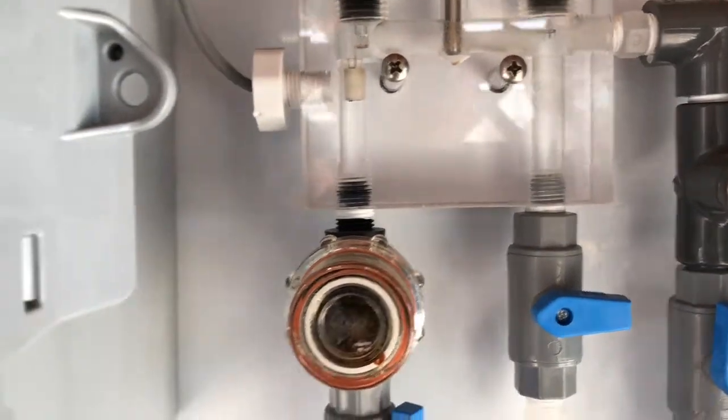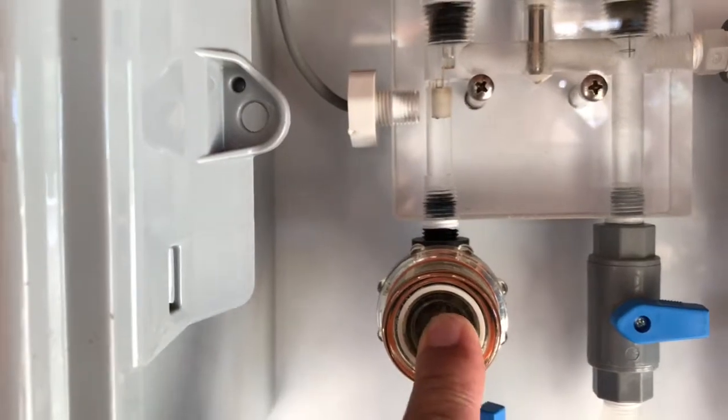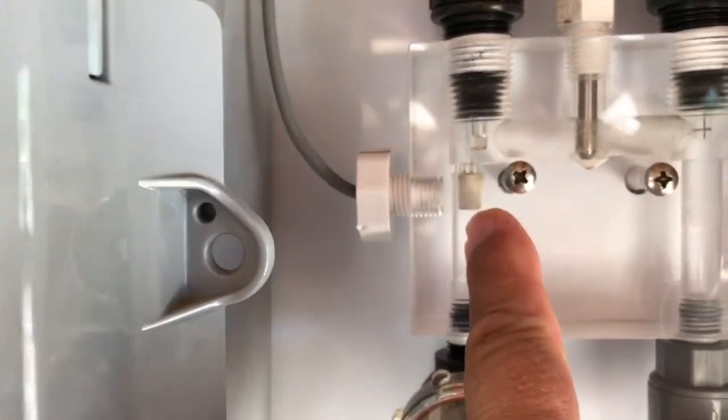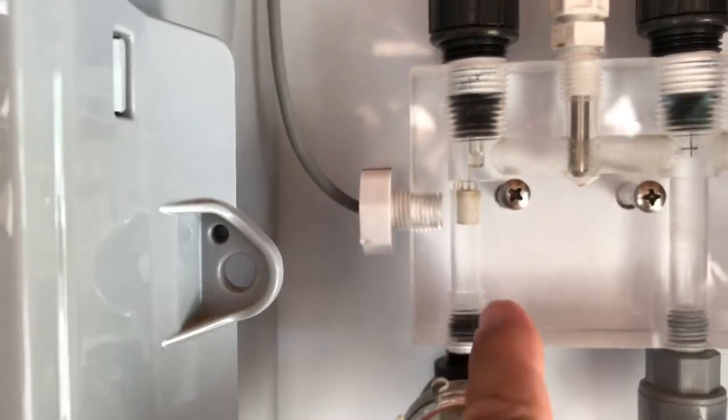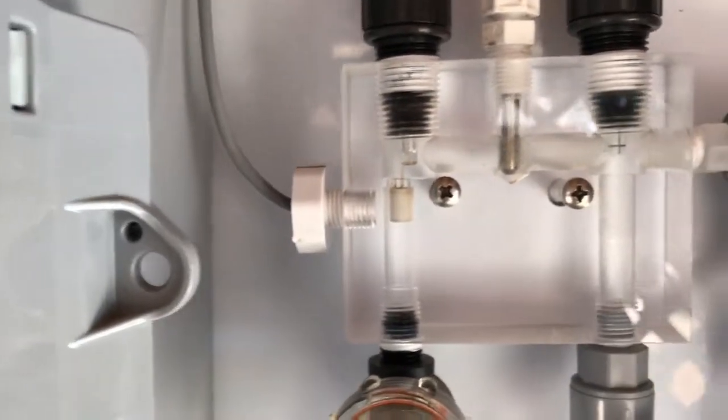One, before you put this filter on, make sure that you have the flow cell magnet which is right there. Make sure it's in this chamber before you thread this on and attach the flow cell to the backboard.